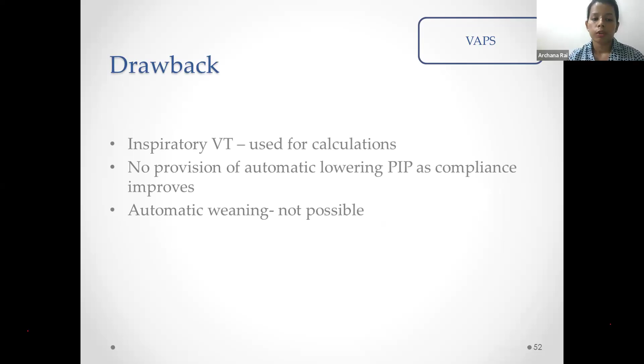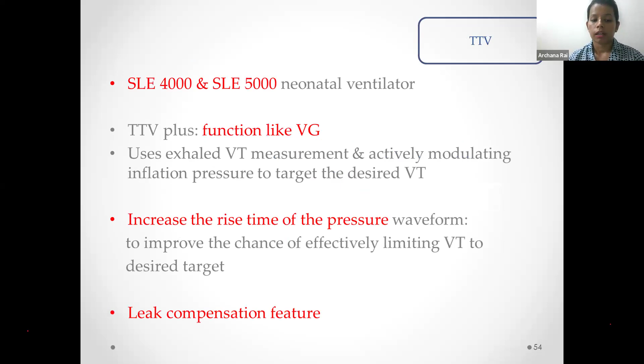What is targeted tidal volume? It is more or less like VG. It is a mode in SLE 4000 or 5000 ventilators. In this, the only extra is that it uses the increase in the rise time of the pressure waveform to effectively limit the tidal volume to the desired target, and leak compensation is also there.